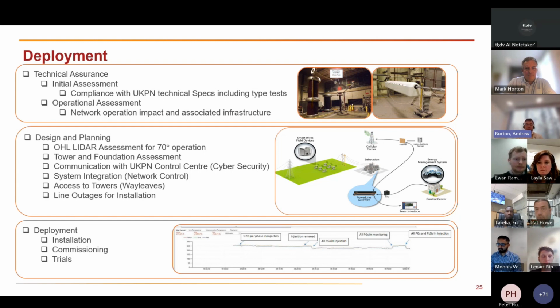We had to do the tower and foundation assessment, understanding the impact on the connections to the tower and the sag on the overhead line. We did a LiDAR assessment, and also increased the operating temperature of the line to 70 degrees, which also impacts the overhead line. So we had to investigate the swing and sag, and what constraints were on site, including anything that might interfere with the overhang.